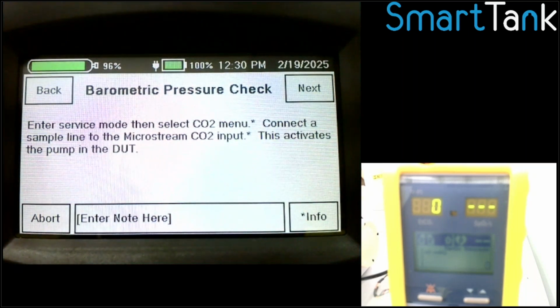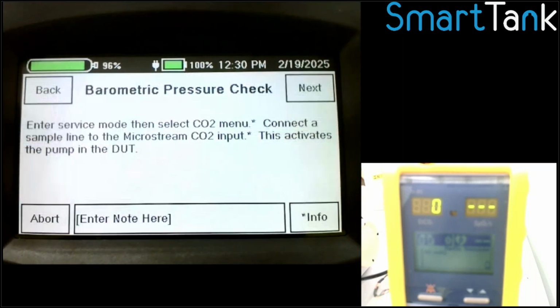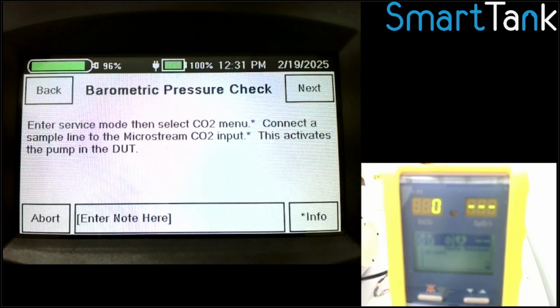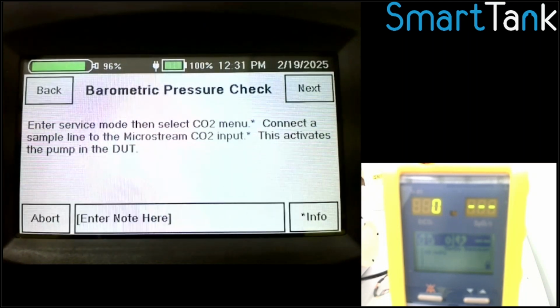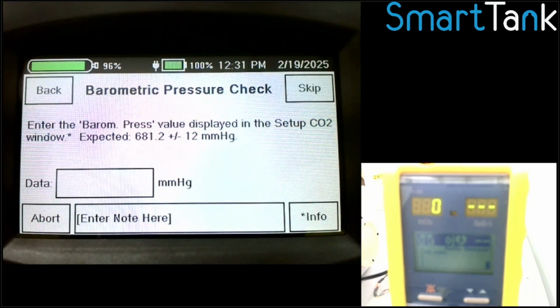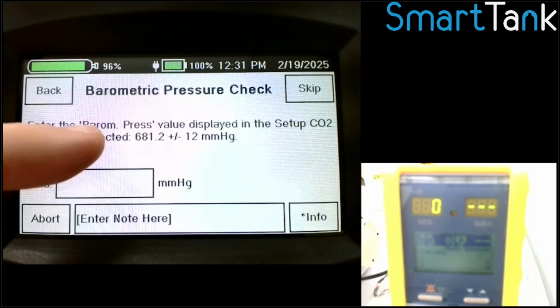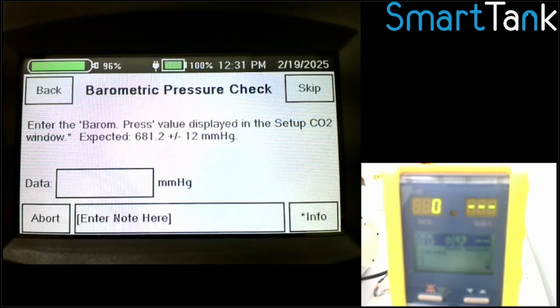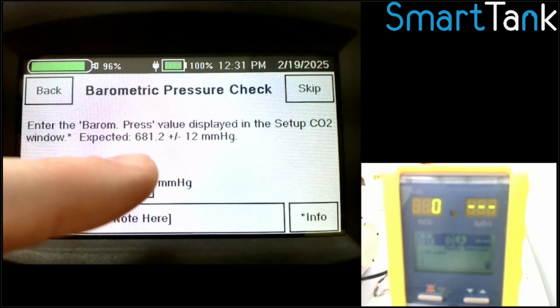So again, the goal is to prevent you from having to go find a service manual. But if you do this 5 times a day and you know it all by heart, then you don't have to dive into these info screens. You can just go through these screens as fast as you want. So in this case, we're not going to actually do this. I'm not going to move the yellow over to get a reading. But it's asking me to enter this barometric pressure that would be on the 3015A screen. We're just simulating this. And it's telling me it wants 681 plus or minus 12.